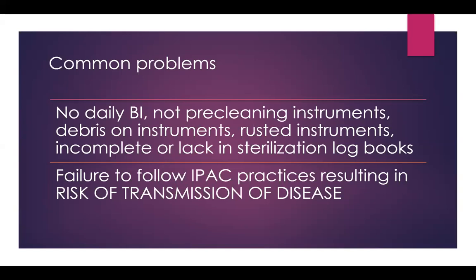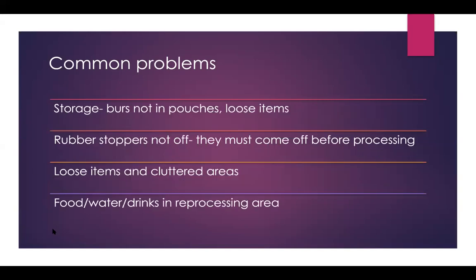Failure to follow IPAC practices results in a risk of transmission of disease. Also, storage of burrs not in pouches and loose items — even if they are brand new burrs in a burr block, either sterilize them and keep them pouched or keep them in their original packaging. You can't have loose burrs in a drawer or loose instruments or loose items for any reason whatsoever.